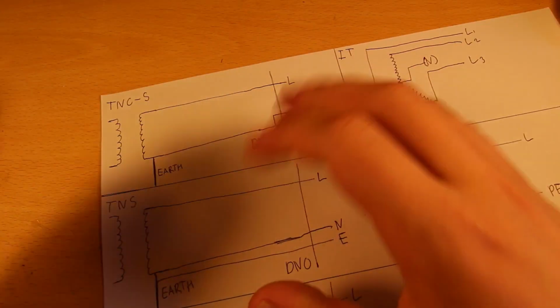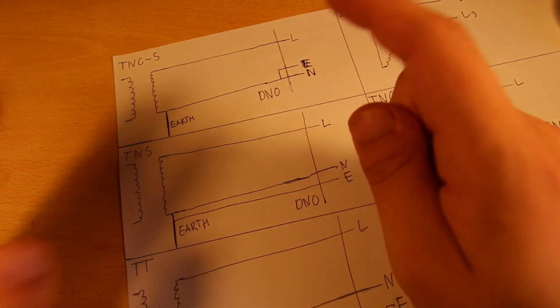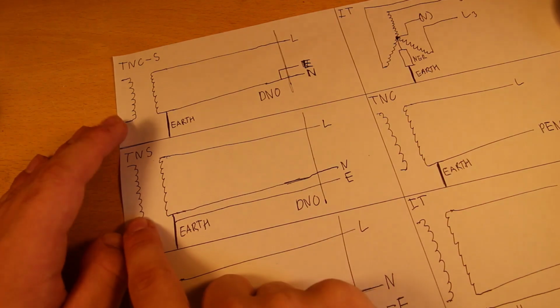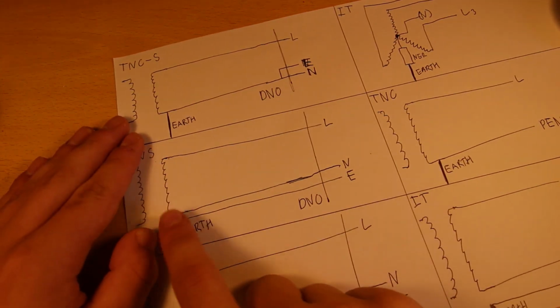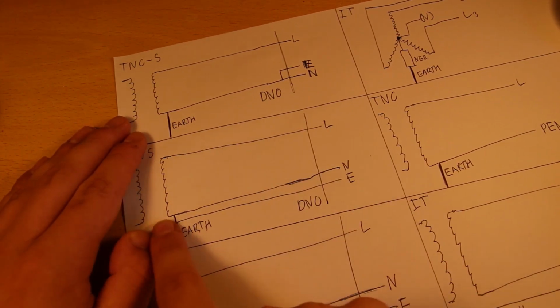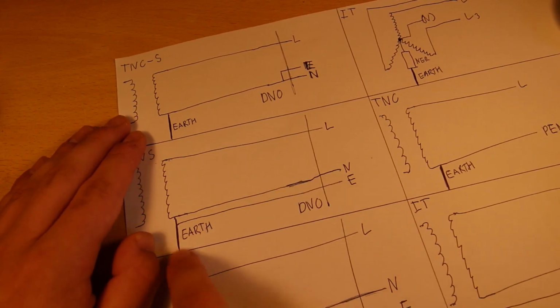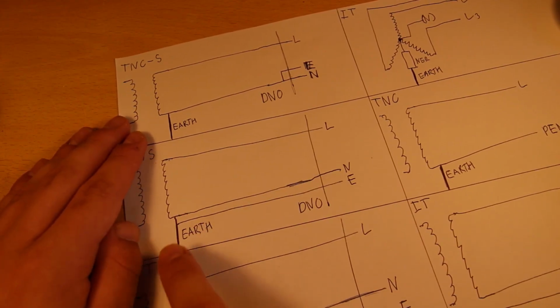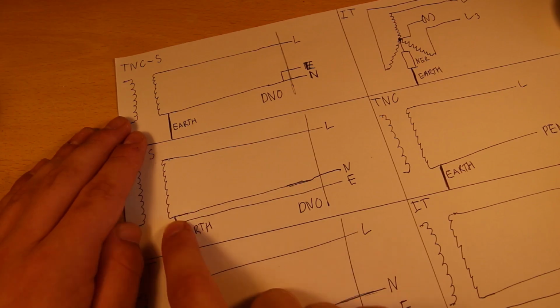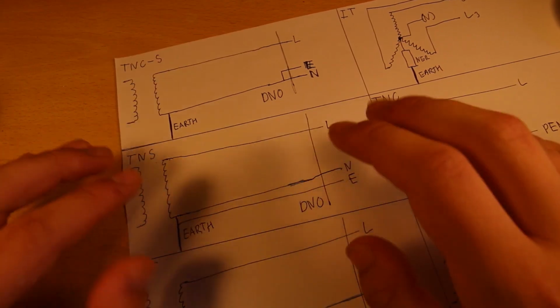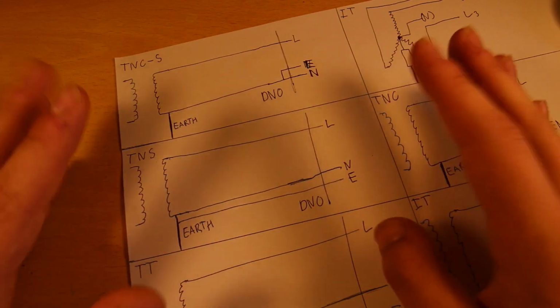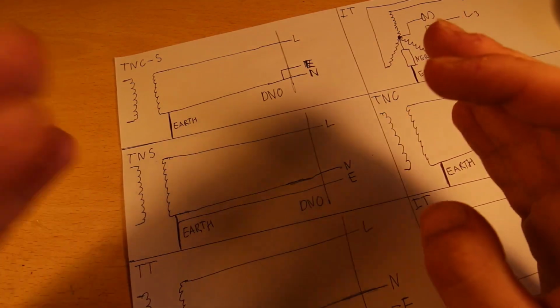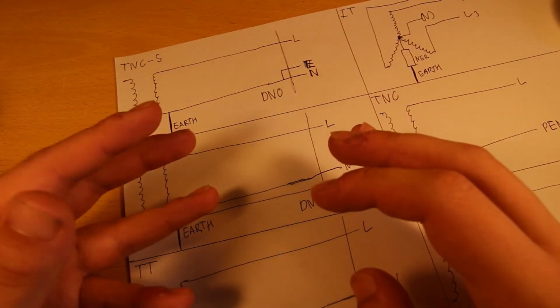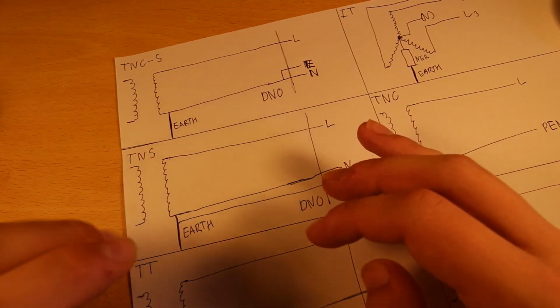This, I say, is the most common one. It has issues, we'll get onto that in a second. We then have TNS, which is earth, neutral, separate. So again, 11 kV comes in here, we have the secondary winding. Live goes off, neutral goes off. The neutral is earthed by the supplier here, but there is then a separate earth which goes from here to the load. This is the best option, but they got rid of it because of the additional expense, where you were running 3 cables rather than 2.